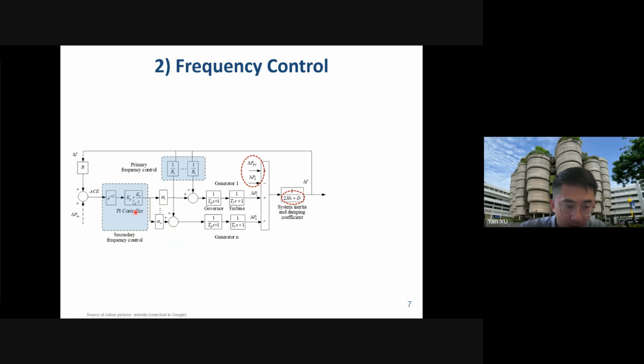Then we will have a secondary control block unit here. You can see that this secondary control block is based on the PI controller, the so-called proportional integral controller. You can see we have two units, one is proportional, another one is integral. This proportional integral controller is able to eliminate the frequency error, delta F. So you can see the delta F will first go through this B, which is also a coefficient. Then if this system is connected with a neighboring system, there will be a tie line connection. So we also take this tie line power change as an input. Now they form the signal called ACE, area control error.